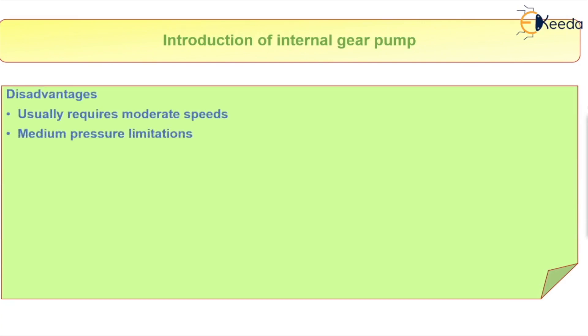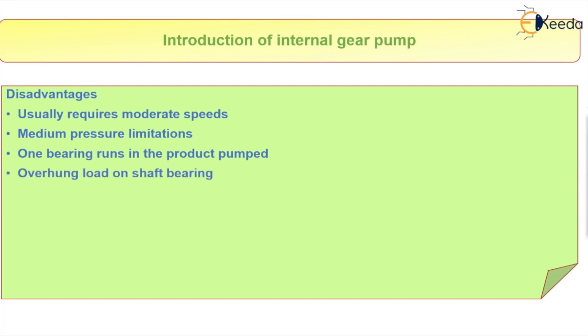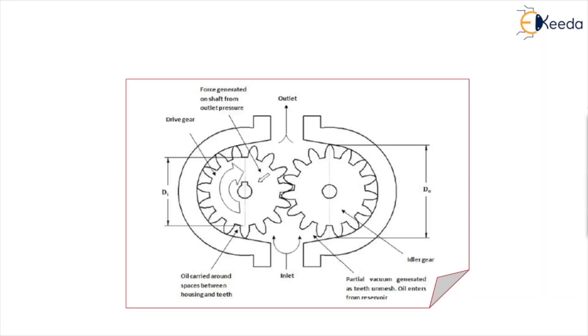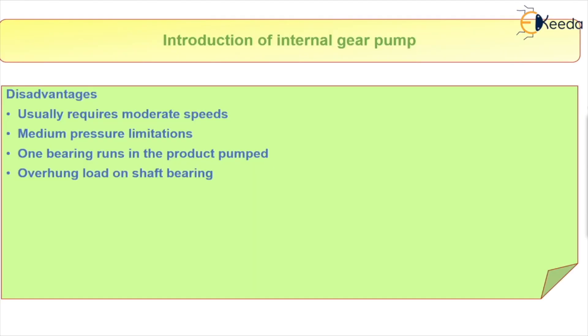Disadvantages of an internal gear pump: it usually requires a moderate speed motor. It has a medium pressure limitation. One bearing runs in the product being pumped, and there is an overhung load on the shaft bearing.